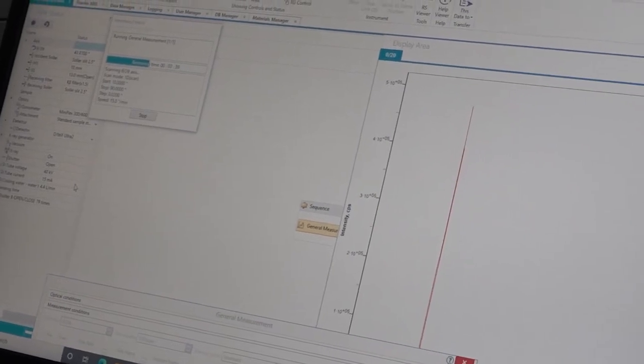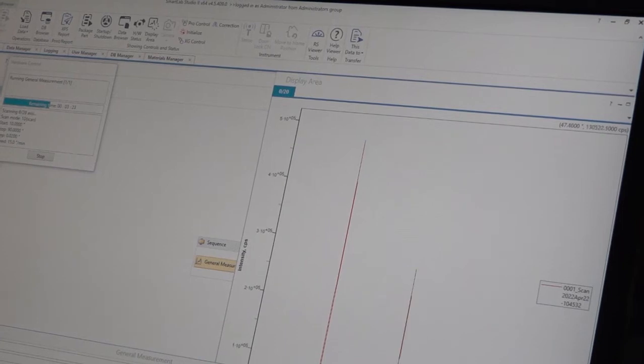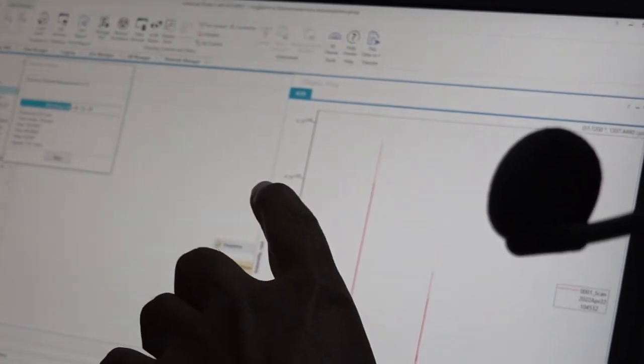For each sample, the startup and shutdown values have to be arranged. Startup is the raising. Yes, I only created that table. See, what will happen? You have to increase the X-ray power slowly. But if I ask you to do it manually, sometimes you can go suddenly to 40, 50. So for that reason I made one table for automatic operation. If you run that table, no need to change manually. Whatever time I have given there, accordingly it will go.